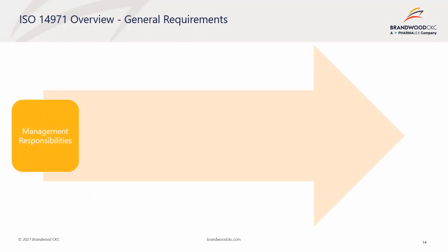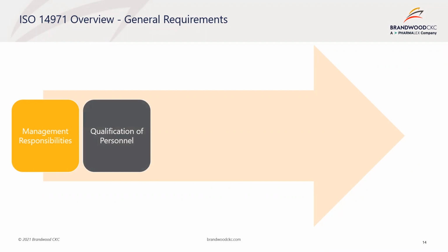Management responsibilities. What roles within the organization will be responsible and have authority for conducting the various risk management activities? This is typically defined within the organization's QMS, typically in the risk management SOP or plan. It includes those overall responsible for the process as assigned by top management. Qualification or competency must be defined for those involved in the risk management processes. For example, you would expect engineers to contribute to the hazard or risk analysis, or the medical or clinical team to help define potential harm.